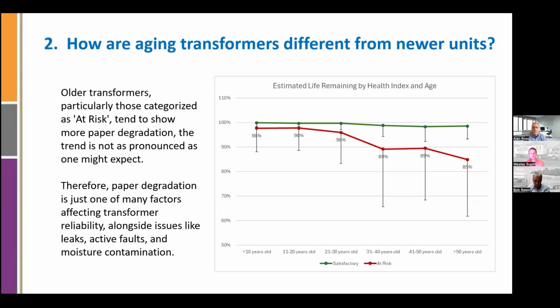So the green line being the satisfactory. This is health index score number 1. This would be akin to IEEE's 4 conditions that they have. It's in the same direction as that. And you look at the paper health over these buckets and in these 2 segmented categories. And what you'll see is that although there is some paper degradation as transformers get older, just because a transformer is older doesn't necessarily mean, like I said before, it's unreliable. And you need to be particularly concerned about transformers that are both older and have abnormal testing results.